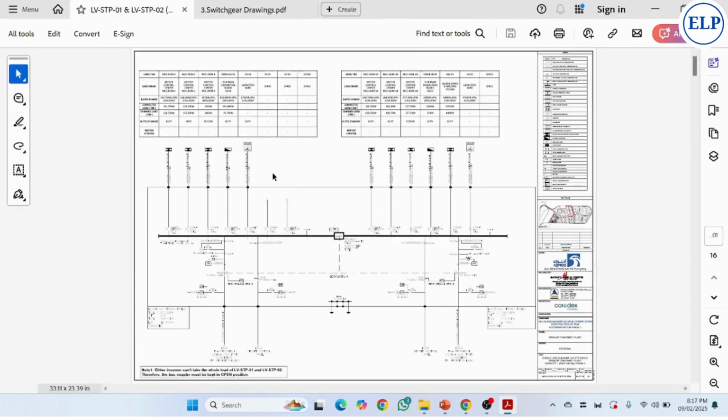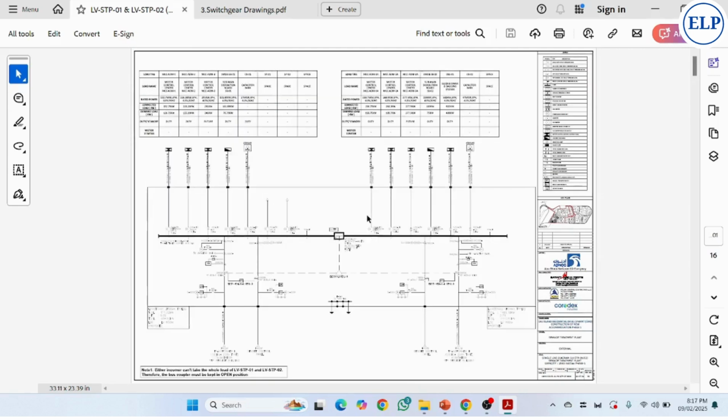Once the single line diagram comes in hand for the project, whoever is a power system engineer would like to build the same network in ETAP and verify and validate whether the selection of the ratings from the client or the contractor side, based upon the power contributions ended by loads, and the components in each and every switchgear panel, satisfies the power flow conditions, meaning power module conditions, under the load condition, short circuit conditions, coordination conditions. We need a tool to analyze this network behavior. Those we can choose presently in ETAP.